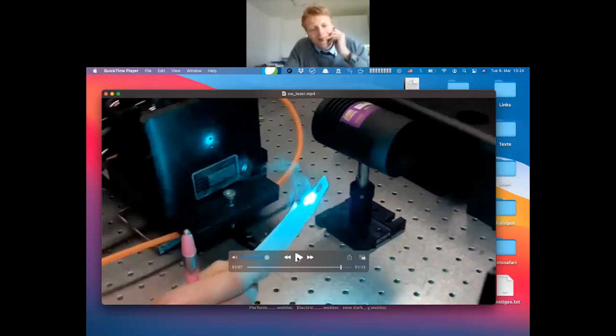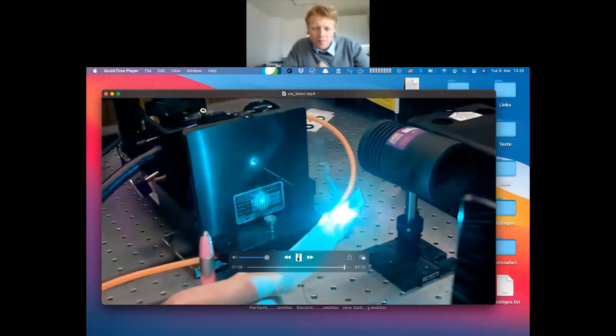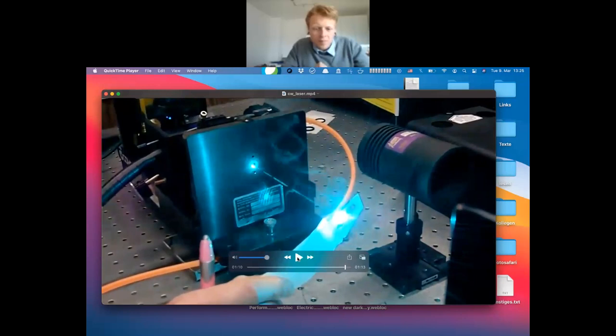And what it does is it's widening up your beam so that you can get a lot of these slits of your lattice in light, increasing the resolution, as we heard. Remember, a few slides ago, we were talking about this equivalence between Fabry-Perot and a lattice-based interferometer, where we said your resolution gets better the more of the slits actually get in contact with light. So this is what you do here. It also has a small Fabry-Perot etalon in between. So this is simply a glass plate, for example, to have yet another wavelength selective element. And this is how it's realized.